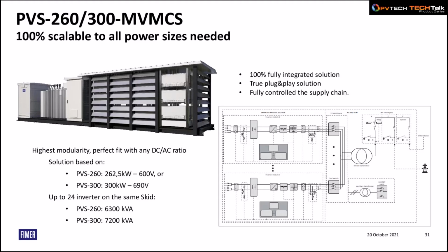The single line diagram is showing how the system looks internally. We have the very same medium voltage part with the medium voltage cubicle, the medium voltage, low voltage, medium voltage step up transformer, and the key factor is also the low voltage compartment where all the 24 power modules are individually protected in order to preserve the granularity, but also the selectivity in case of single point of failures. All of these components are fully integrated in our factories, so as to offer a true plug-and-play solution and fully control the supply chain. So these components are manufactured and integrated in our factories.